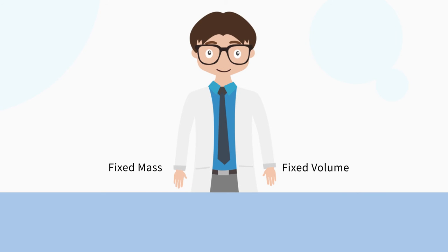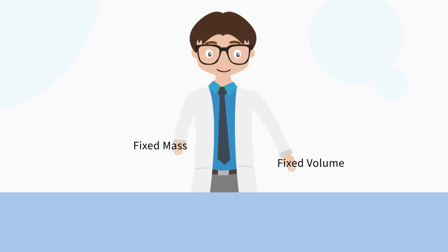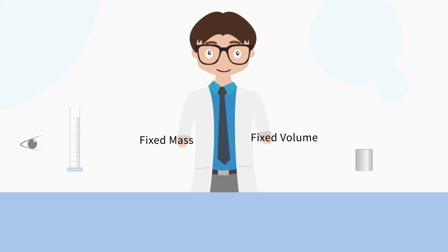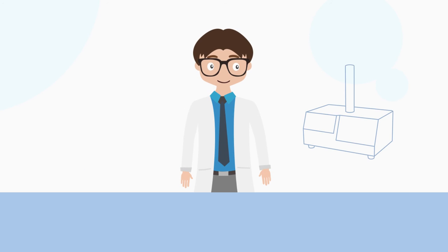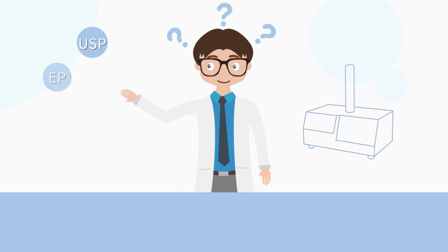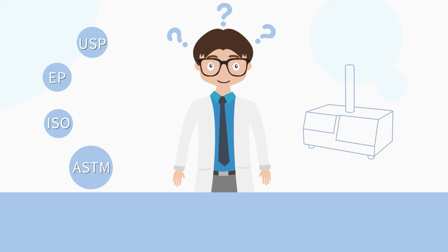The two techniques are fixed mass or fixed volume. There is no big difference between them. The main concern for customers is whether the instrument complies with international standards such as USP, EP, ISO, and ASTM.